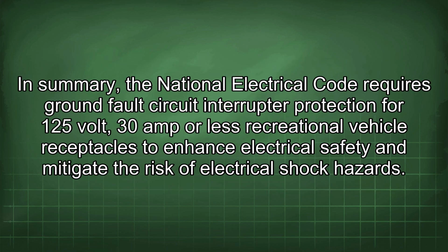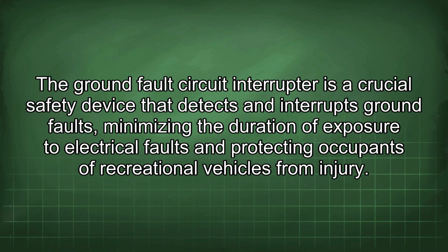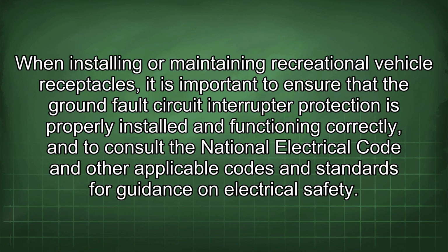In summary, the National Electrical Code requires ground fault circuit interrupter protection for 125-volt, 30-amp or less recreational vehicle receptacles to enhance electrical safety and mitigate the risk of electrical shock hazards. The ground fault circuit interrupter is a crucial safety device that detects and interrupts ground faults, minimizing the duration of exposure to electrical faults and protecting occupants of recreational vehicles from injury.